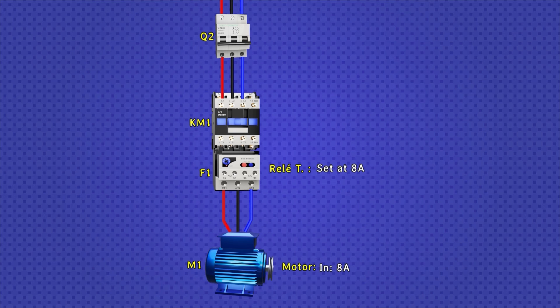Since, if the intensity setting is less than the nominal intensity of the motor, it will not be in danger of failing due to overload, but it will not have maximum performance either. On the other hand, if the current setting is greater than the motor's rated current, then the motor will work at its maximum output. But it will also be prone to being overloaded and the motor winding going bad.